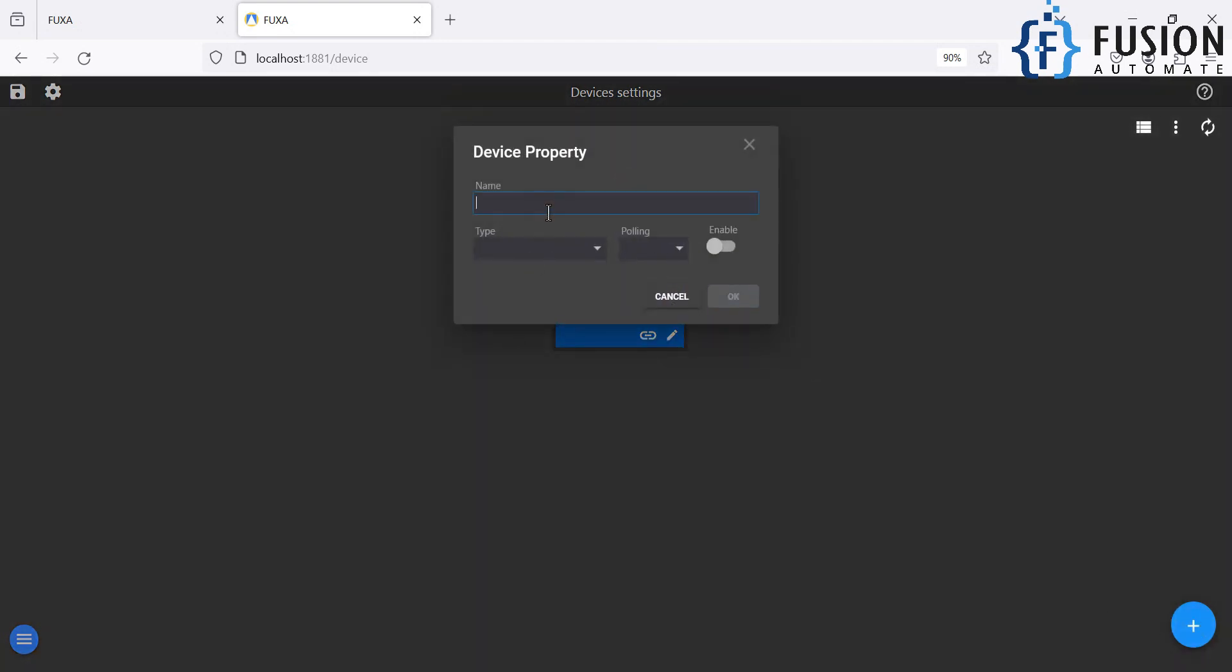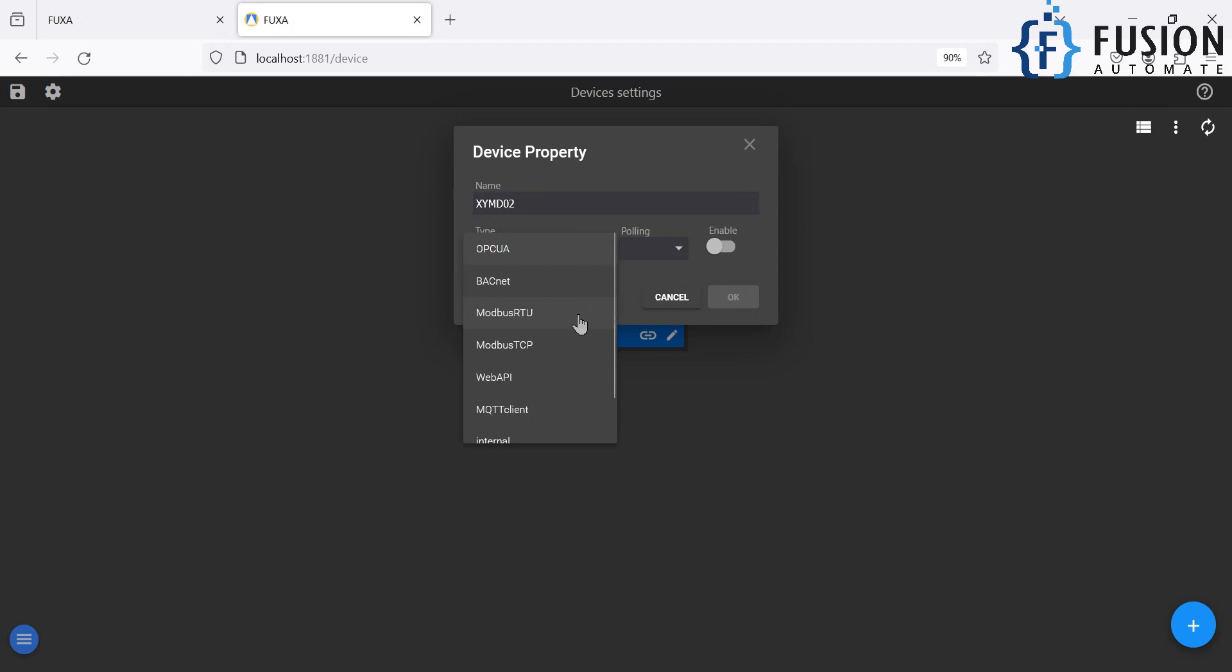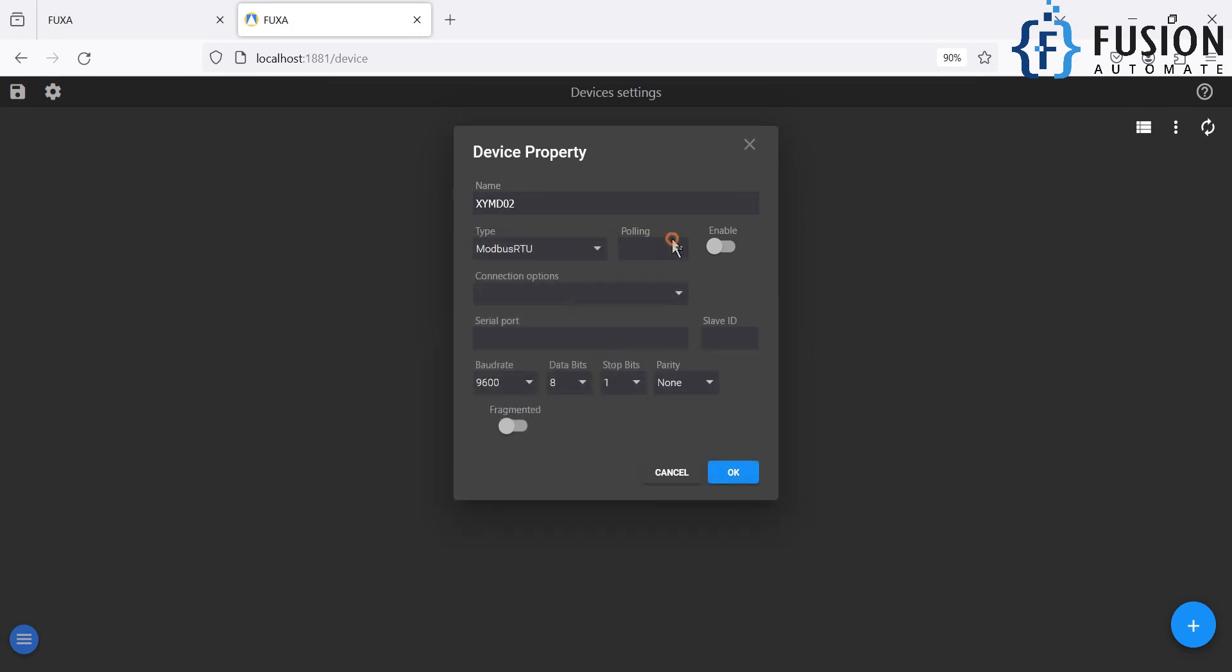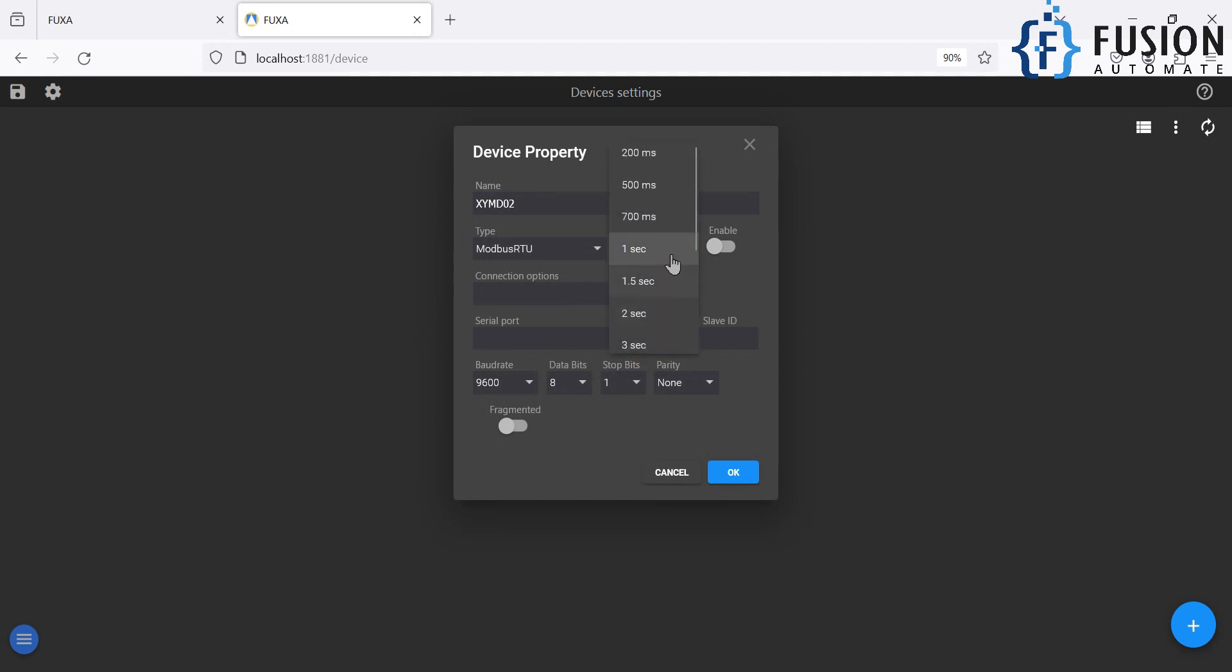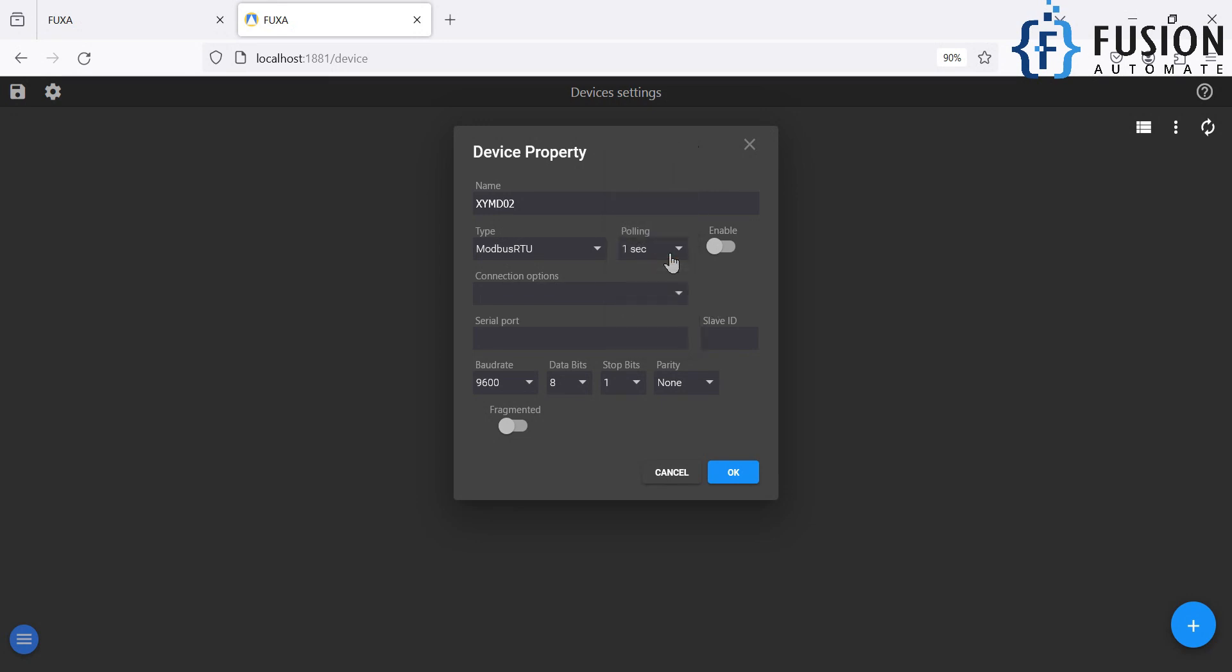So you have to click on this plus icon. You have to provide your device name, which is XYMD02. And in the type you have to select which kind of device you are connecting. So we are connecting to Modbus RTU. The polling is one second. Whatever you want to select, I mean whatever second you want to select as per your requirement you can select, but I'm going to select one second. So it will poll the data from my device at every second. We are going to enable the device. Connection is serial port.